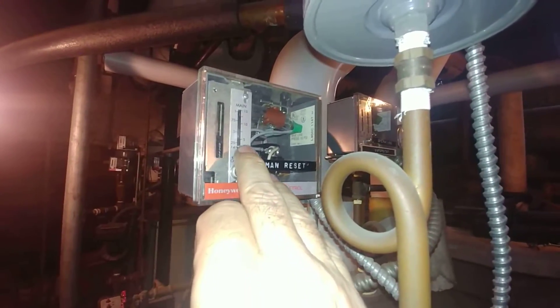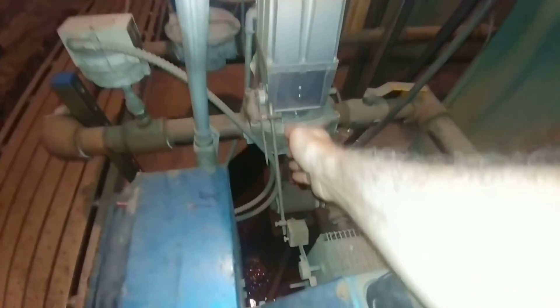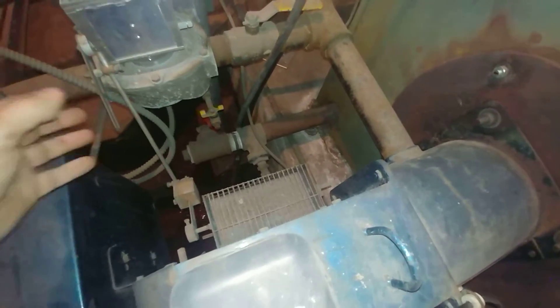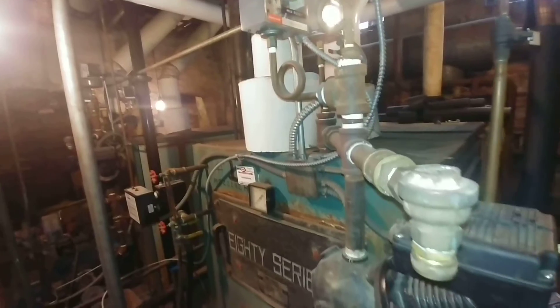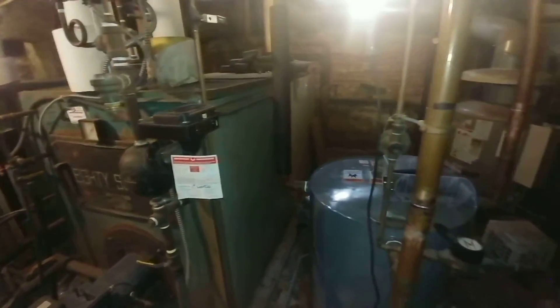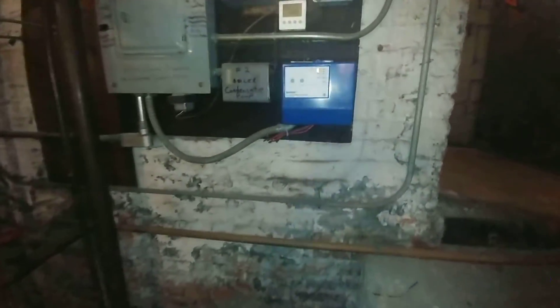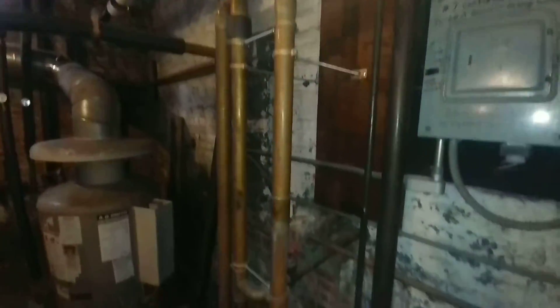There's your safety reset control, which we operate at about two pounds. The system operates low-high-low at about four ounces. When four ounces of pressure is generated, this throttling control throttles the gas and air so that you get good combustion even at low pressure, so it cycles between four and ten ounces. When it kicks off at about 12 ounces — which is usually when the temperature gets to about 20 degrees or below — the system will have a complete burn controlled by the Tekmar. And so that is a false water line with a loop seal rather than a trap, and it seems to work.